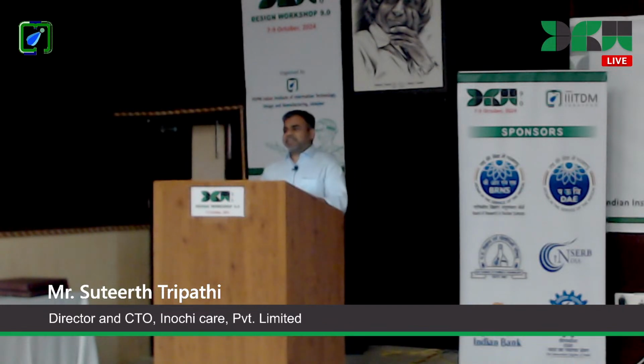Once this risk mitigation exercise is completed, you have your refined design of the product ready. You do not go into production - you go back to the risk assessment again, follow the entire process again, and see if all of your risks have been removed or brought down to an acceptable level for actual field use. Once you have ascertained that no further risk mitigation is required and no further risks remain with the product, that is when you go to the next stage: the actual fabrication of the prototypes and the bench testing of the prototypes.